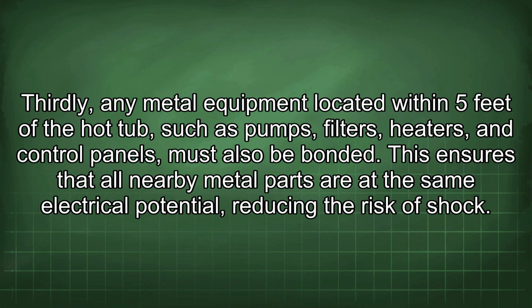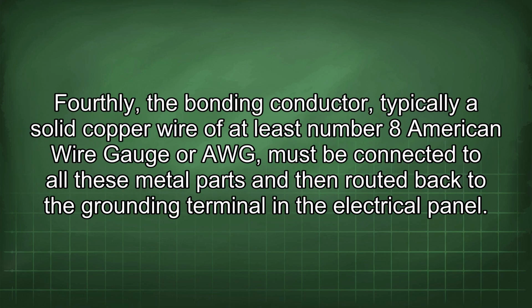Thirdly, any metal equipment located within 5 feet of the hot tub, such as pumps, filters, heaters, and control panels, must also be bonded. This ensures that all nearby metal parts are at the same electrical potential, reducing the risk of shock. Fourthly, the bonding conductor, typically a solid copper wire of at least number 8 American wire gauge, or AWG, must be connected to all these metal parts and then routed back to the grounding terminal in the electrical panel.